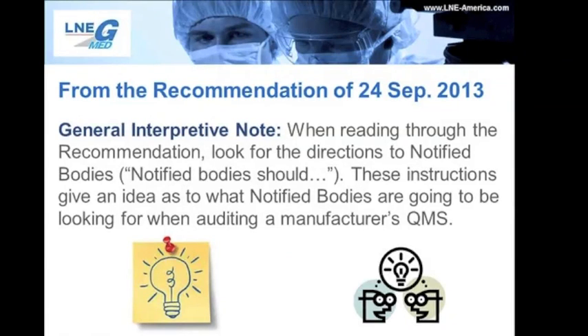So just real quick, before we get into the meat of the recommendation, I want to give you a quick interpretive note that will help you answer the question of what is my notified body going to want to see. When reading the recommendation, you'll notice that it's written as instructions to the notified body. You can use these instructions as a way to figure out what your notified body is going to want to see or look for when auditing your quality management system. So that's an important note.